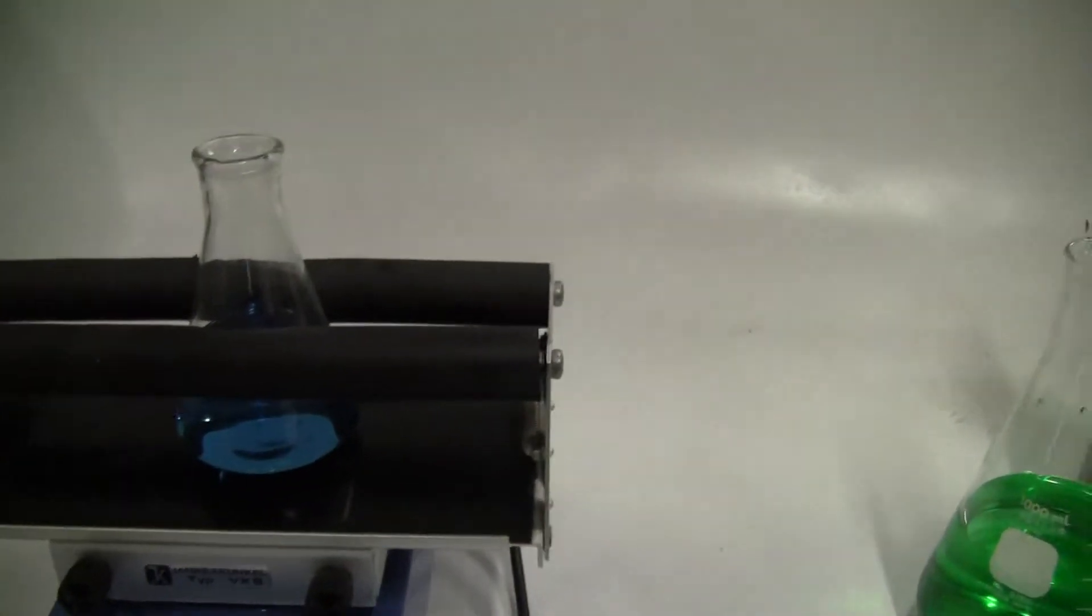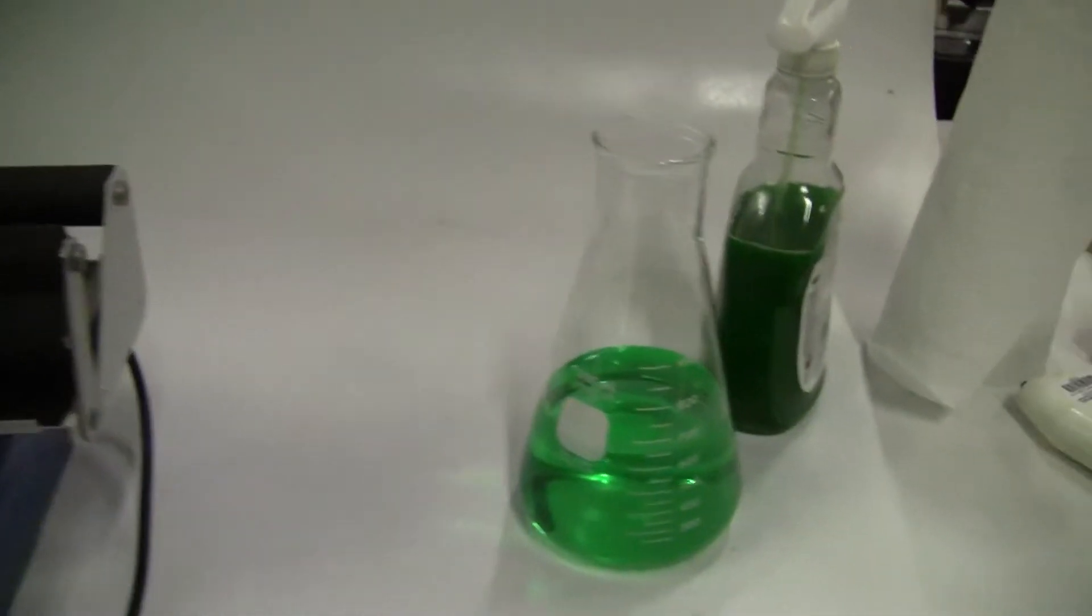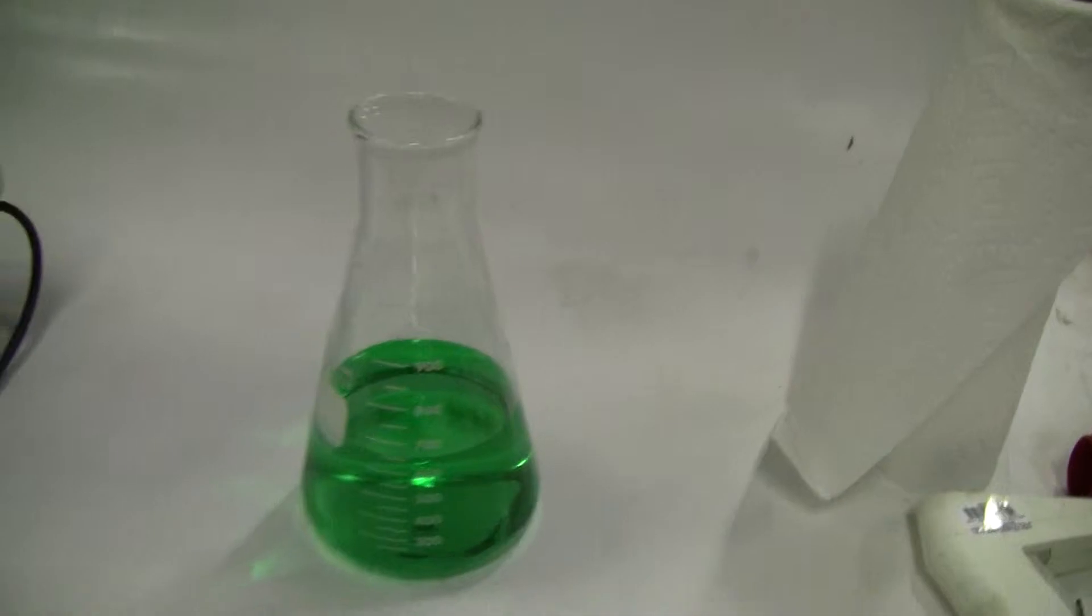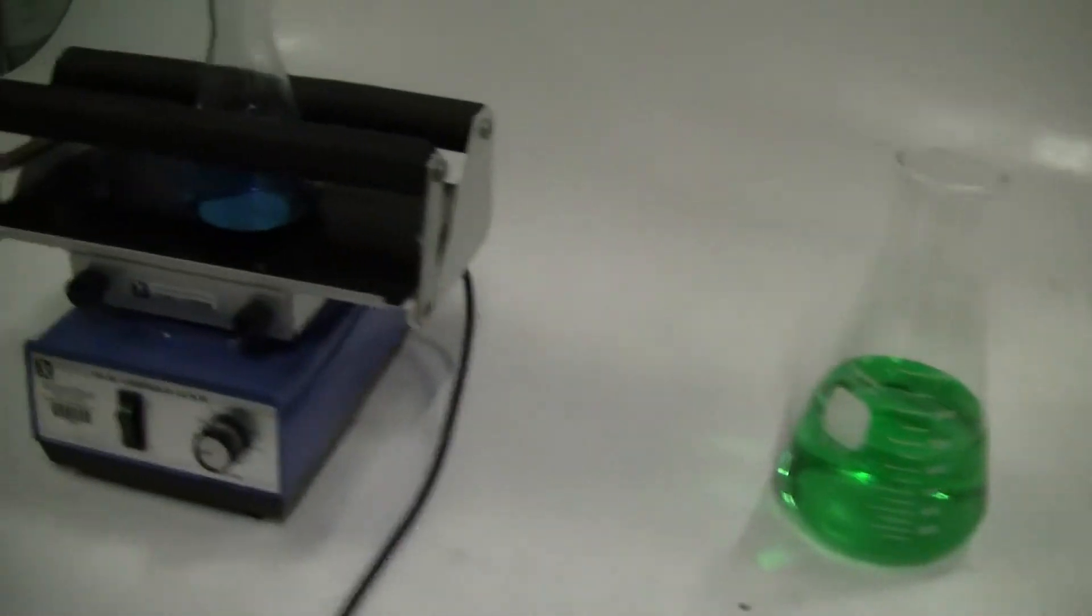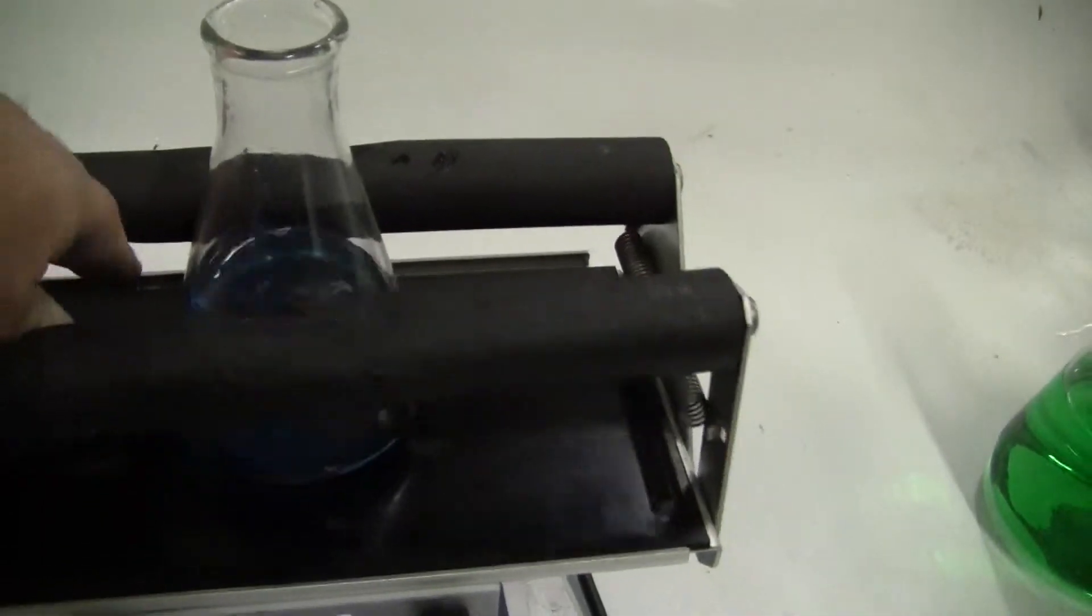We have it listed as holding a max of two 500 milliliter Erlenmeyer flasks, but as I'll show you in a minute, we have been able to run it with a 1 liter flask in there. It's got a universal holder, spring-loaded, so it's easy in and easy out.